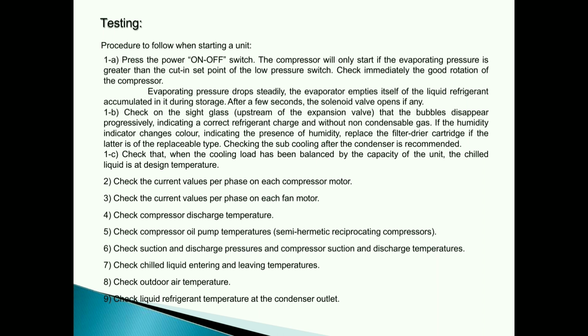1-B. Check on the sight glass, upstream of the expansion valve, that the bubbles disappear progressively, indicating a correct refrigerant charge and without non-condensable gas. If the humidity indicator changes color, indicating the presence of humidity, replace the filter dryer cartridge if the latter is of the replaceable type. Checking the subcooling after the condenser is recommended. 1-C. Check that, when the cooling load has been balanced by the capacity of the unit, the chilled liquid is at design temperature.